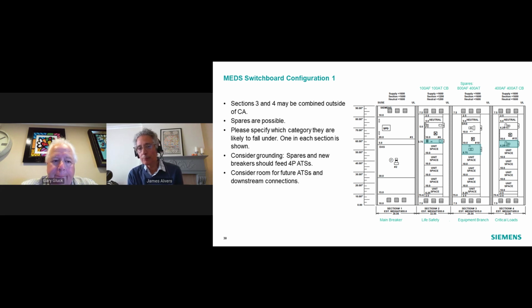The 1200 amp distribution breaker in the equipment branch is actually a 1200 amp frame with a 1000 amp trip on the one line. So if that breaker were a standard thermal mag with a non-interchangeable trip, you would not need arc flash protection there. Often these breakers are selectively coordinated, so you may have a solid state breaker there, in which case, even at a 1000 amp trip, you would need the arc mitigation. Okay.